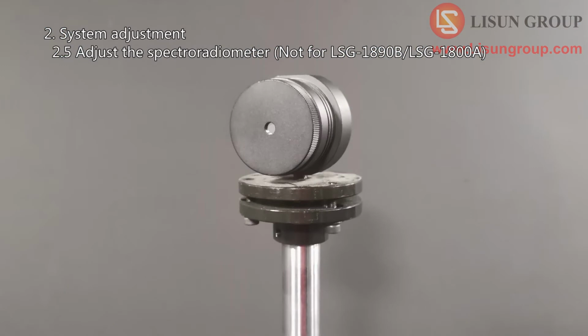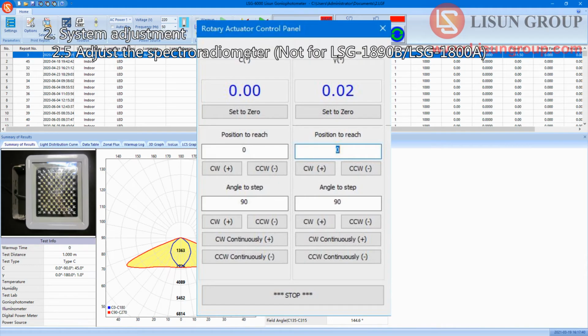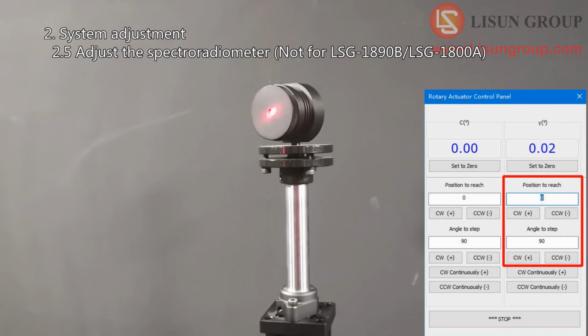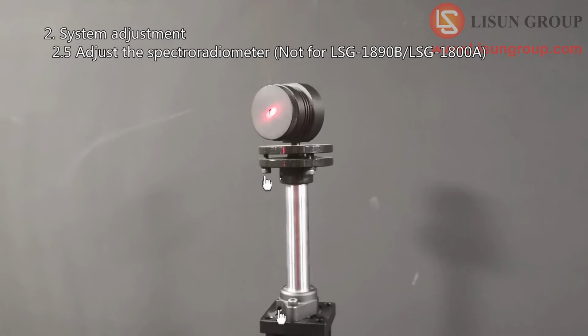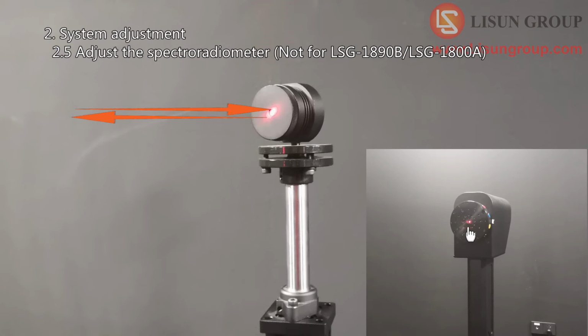Install the mirror tool on the sleeve of the optical fiber. Rotate the gamma angle on the software to aim the laser at the mirror tool. Now you need to adjust the gamma angle, the height and direction of the sleeve. Make sure that the laser from the main arm of the goniophotometer goes to the center of the mirror tool, and the reflected laser goes to the original position.